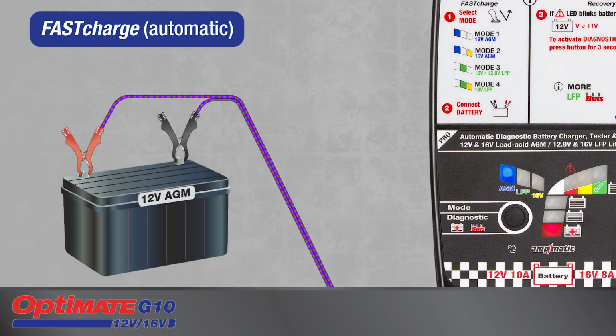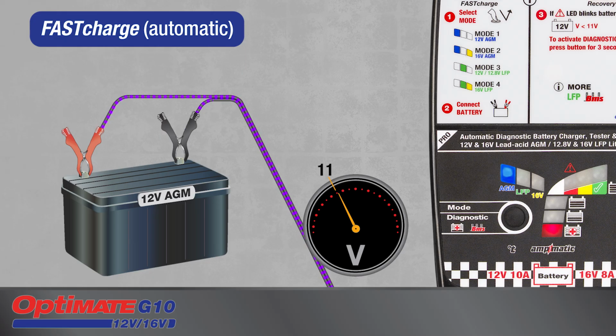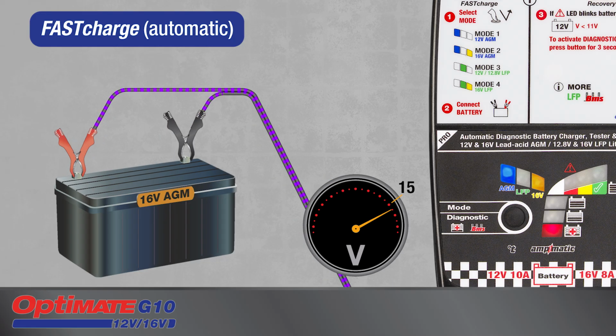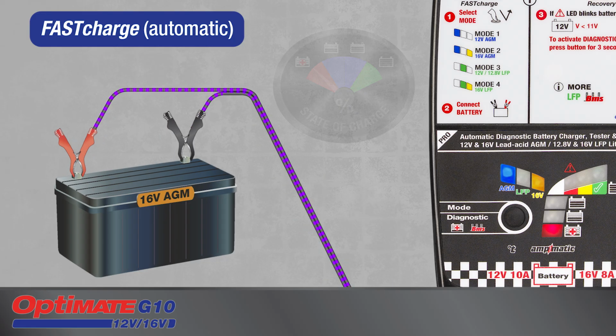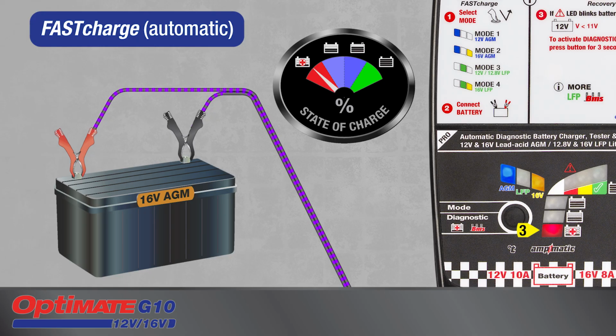Charging starts automatically if the battery's voltage is 11 volts or higher for a 12V battery or 15 volts or higher for a 16V battery. Red LED 3 indicates the battery is below 50% state of charge. LED 3 will remain lit for a minimum of 10 seconds whilst the program verifies battery health.